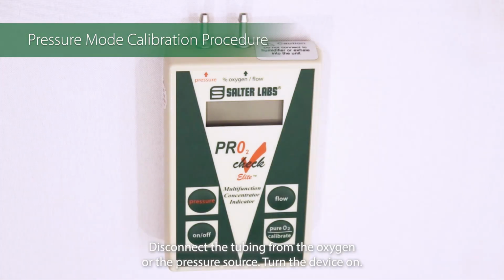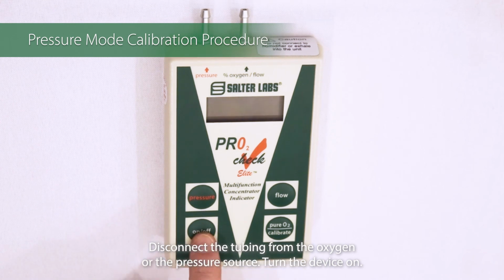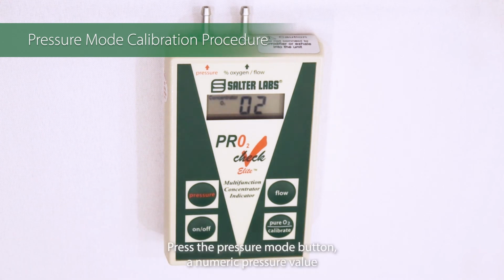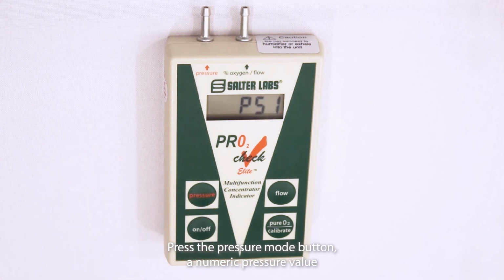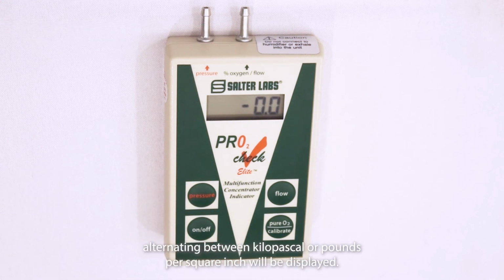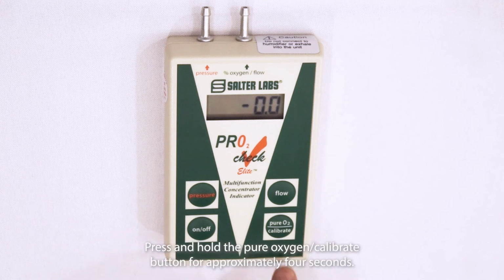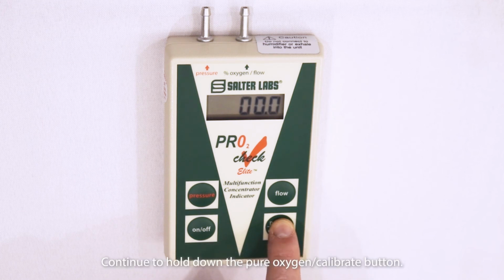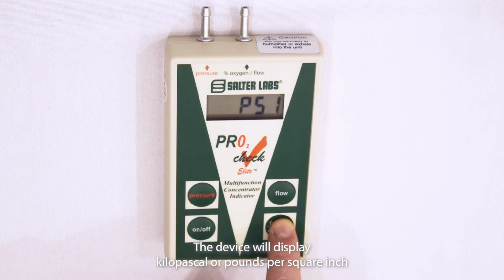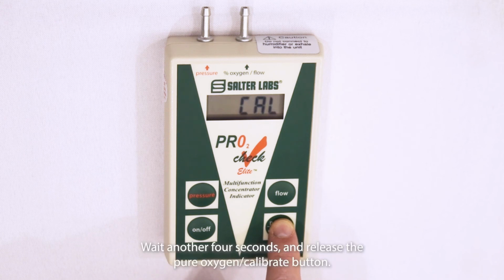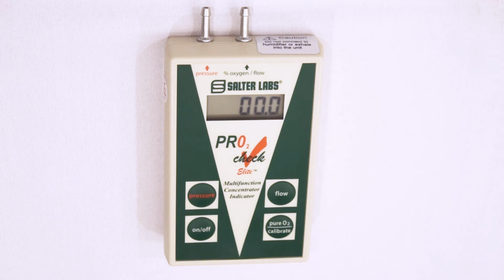Disconnect the tubing from the oxygen or the pressure source. Turn the device on. Press the Pressure Mode button. A numeric pressure value alternating between kilopascal or pounds per square inch will be displayed. Press and hold the Pure Oxygen Calibrate button for approximately 4 seconds. Continue to hold down the Oxygen Calibrate button. The device will display kilopascal or pounds per square inch and alternately flash 0.0 and Cal. Wait another 4 seconds and release the Pure Oxygen Calibrate button. The pressure mode is now calibrated.